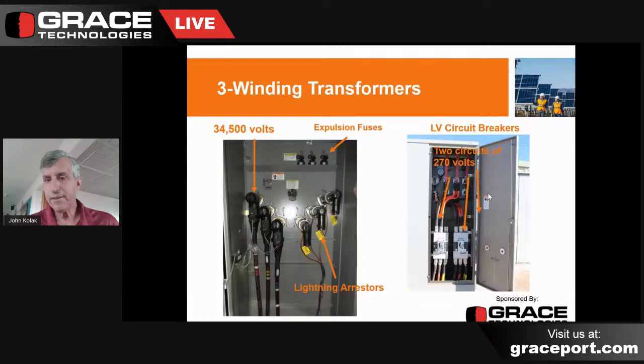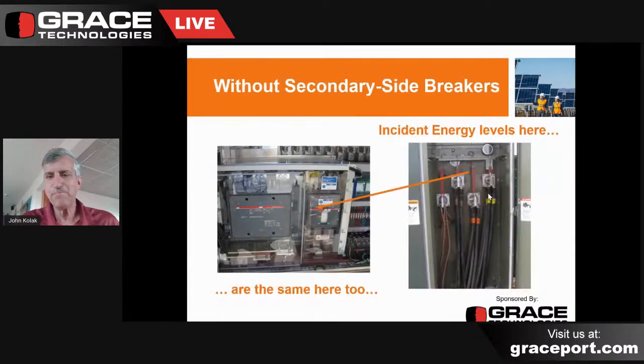Yet in this case, we have parallel systems, two 270 volt circuits that come out of there, and then the circuit breakers in that system are right in the pad mount transformer itself. And we're going to talk about that from an incident energy calculation standpoint here in just a second. We'll go on to the next slide.